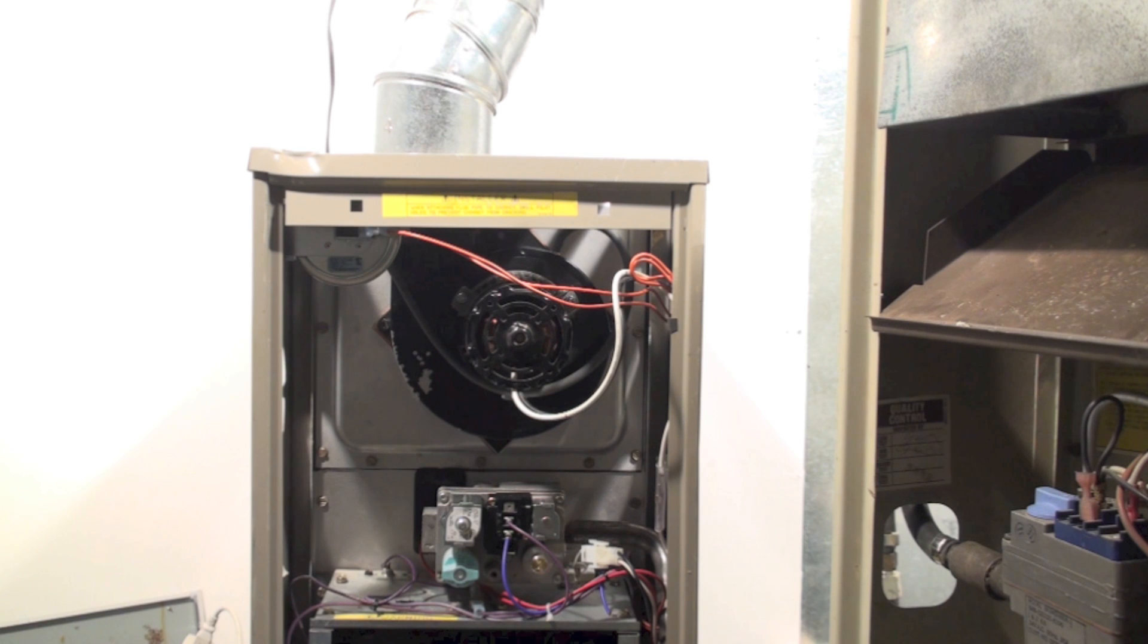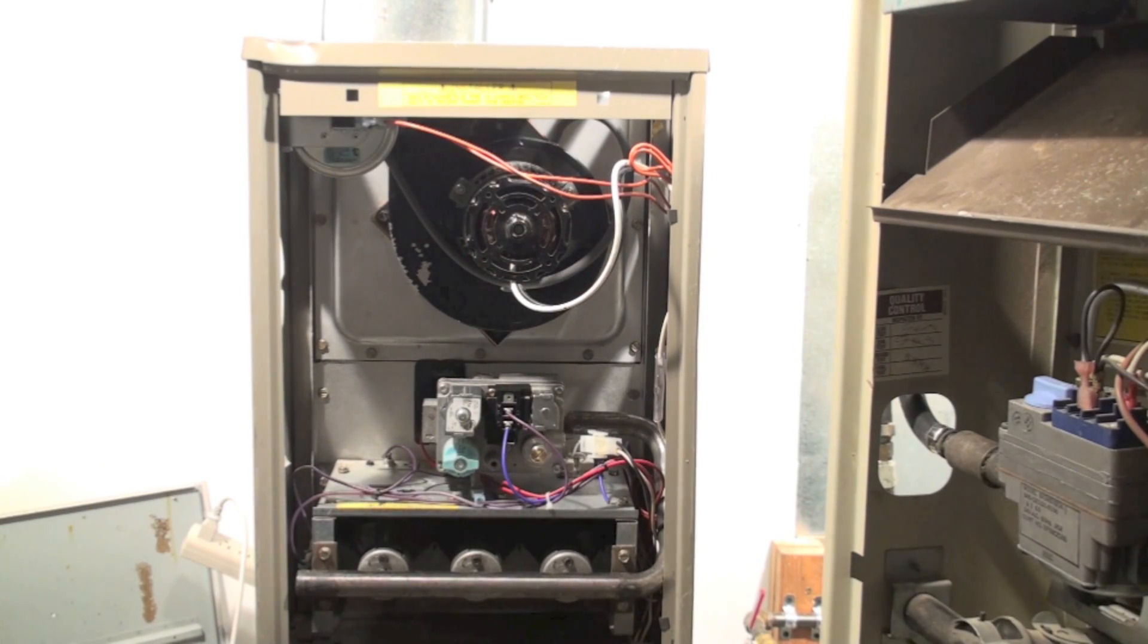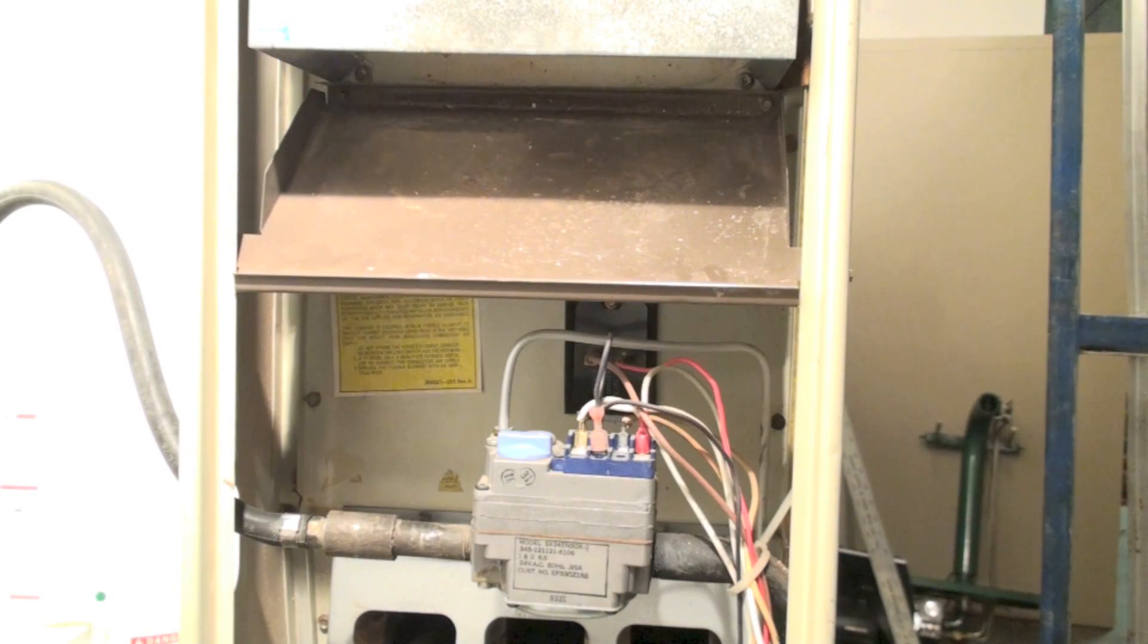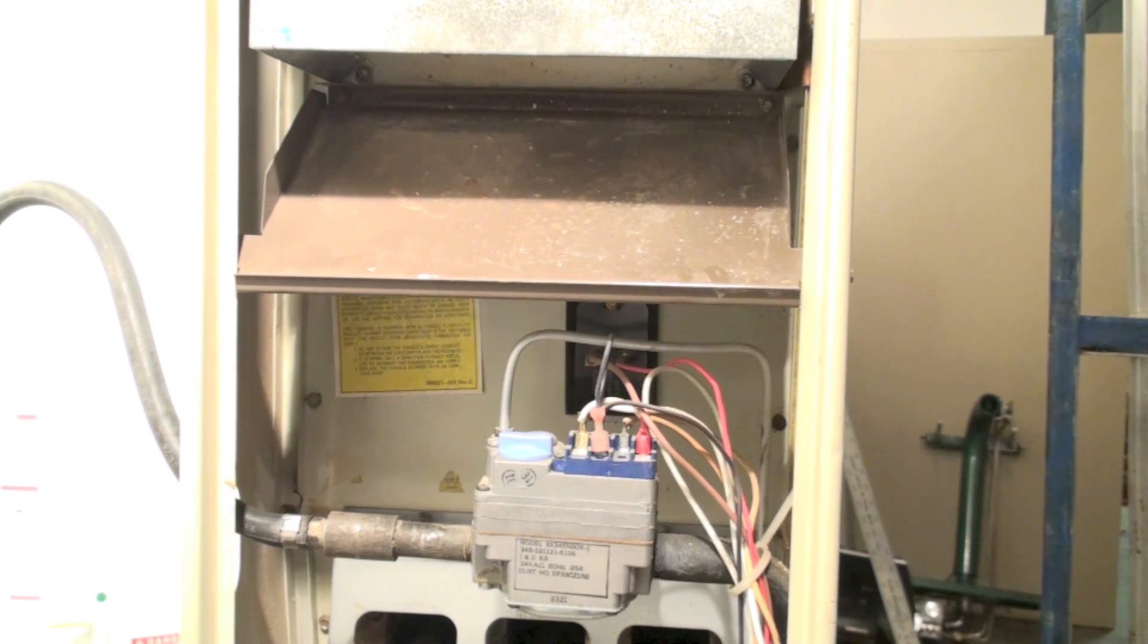These newer furnaces had to have some sort of rating that everyone could depend on. So the older furnaces, if you were looking at the AFUE of this furnace, it would actually be more like somewhere between 55 and 65% efficient.